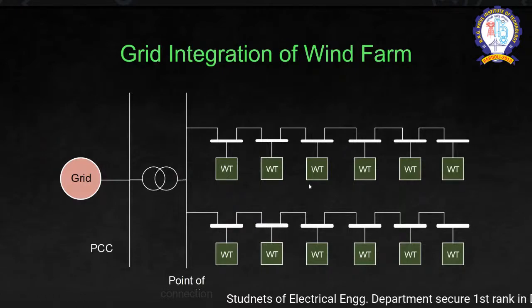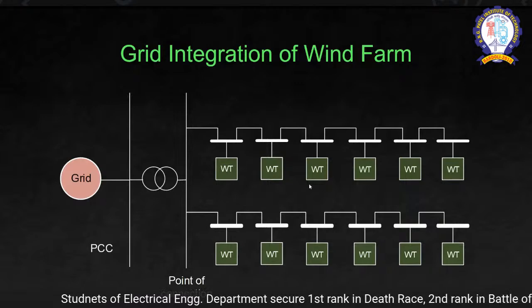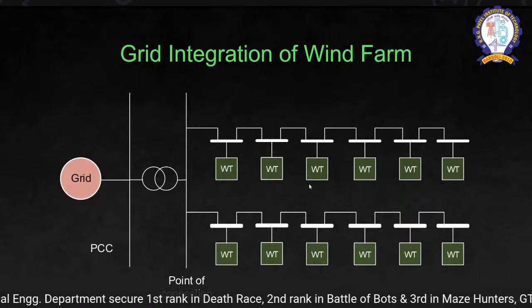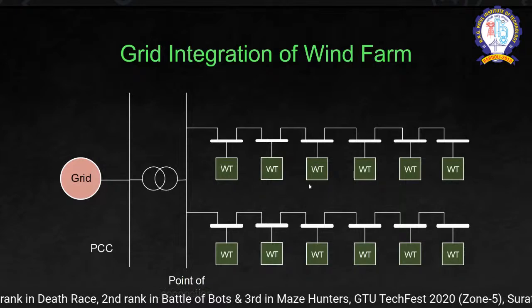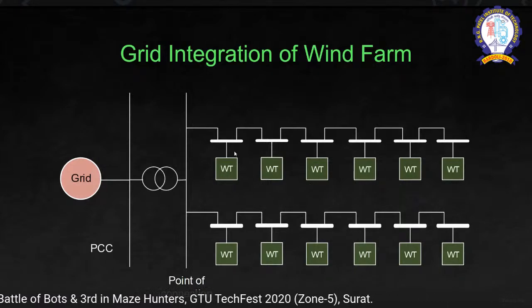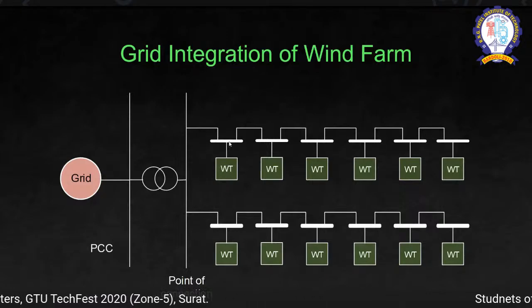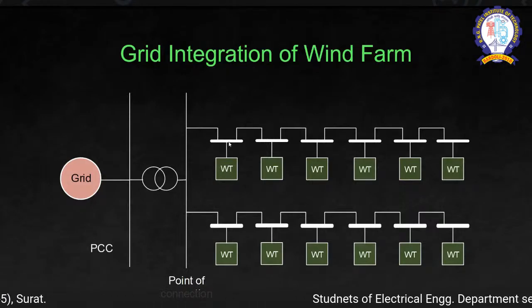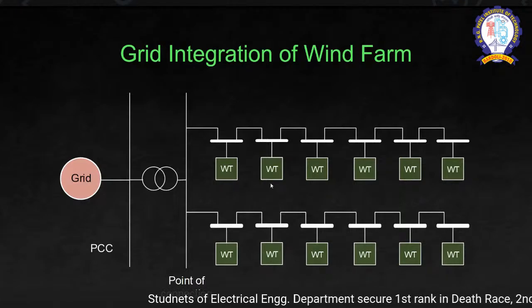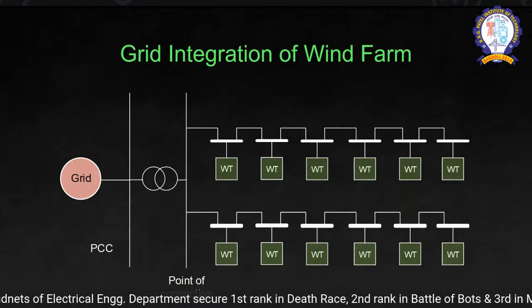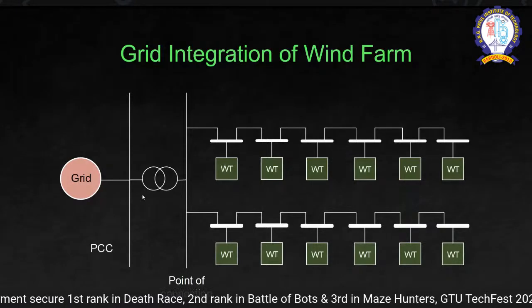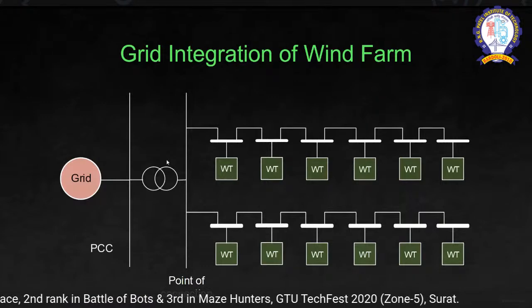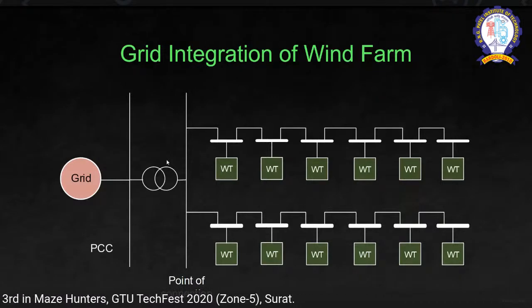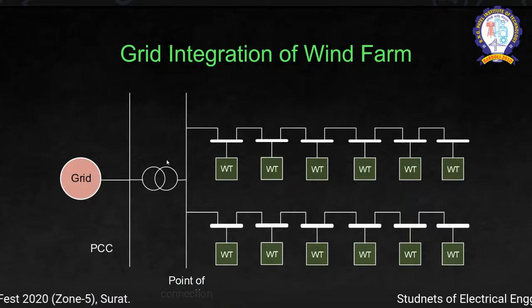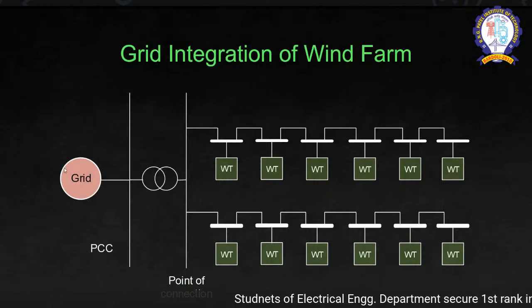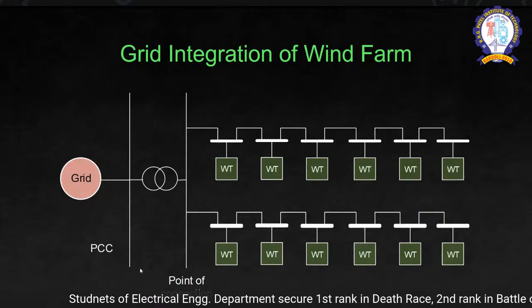Now, usually we are working in the wind farm structure, where multiple wind turbines are connected. These are the multiple wind turbines. Over here, there is one common bus where the transformer and other assemblies have to be accommodated. These wind turbines are connected with the point of common connection. Then we have the main transformer, which we call the substation transformer, where the entire power plant is merged, and then it is integrated with the grid. So this is our PCC, point of common coupling.